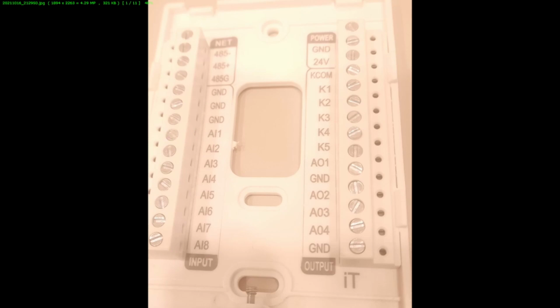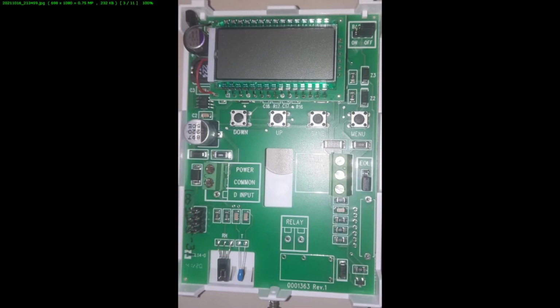So what I have set up is I have centralized iStats, and each one controls up to 5 zones. And so I have up to 4 remote temperature sensors that are in rooms that don't have an iStat, where I'm just recording the temperature in that room, and that is then used to control its corresponding actuator to open up the appropriate zone valves. The device also then has an onboard temperature sensor, which can be used to control one of the K relays as well. While we're talking about sensors, let's also look at the dew point control.